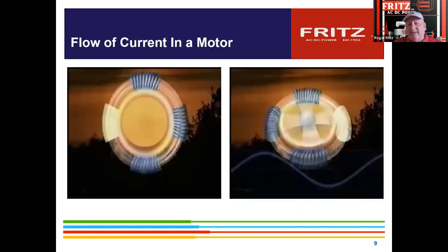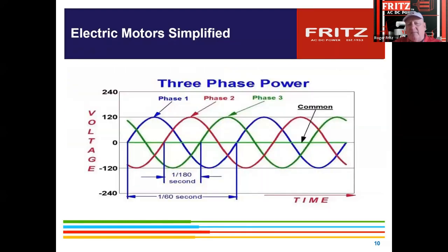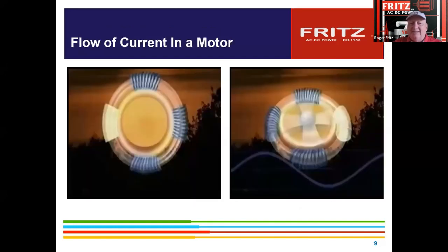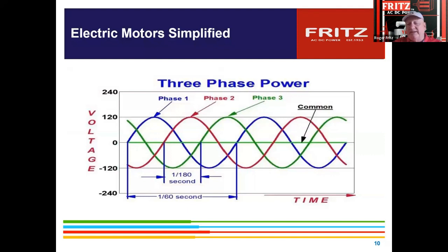And then the difference: this shows a single phase set of coils on a 4-pole machine, where this actually shows all the sine waves of 3-phase power, so when you have 3 power lines feeding the motor. One other point is that you can take a single phase input and drive a full 3-phase variable output to the motor, because we're doing it from DC. So there are savings there, because a single phase motor is about 65 to 70% efficient. A 3-phase motor is up in the 90s. And you normally have about a 1.5 to 2% loss in a VFD in its components, but the energy savings and balancing of power definitely correct for that, with efficiency gains.